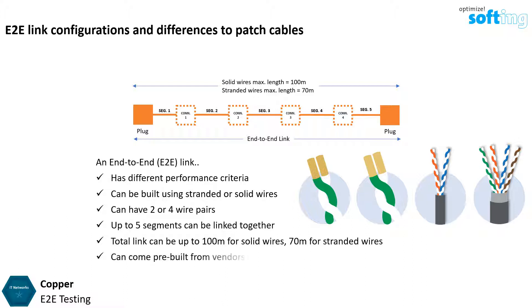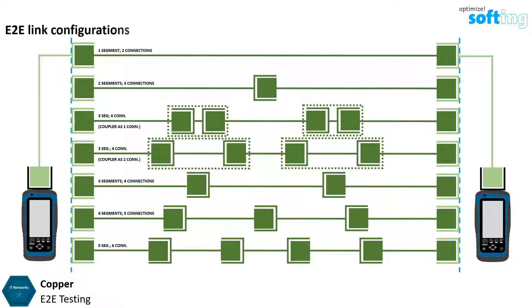An end-to-end link can come pre-built from vendors, or can be assembled in the field using field terminated plugs or sockets. Some end-to-end link configurations can contain segments with plugs or sockets at the cable ends. An end-to-end link can comprise up to 5 segments and 6 connections.